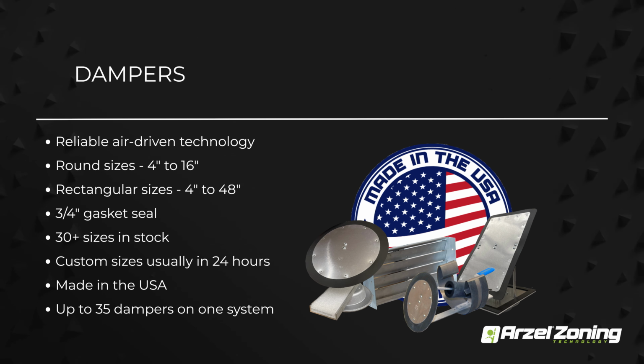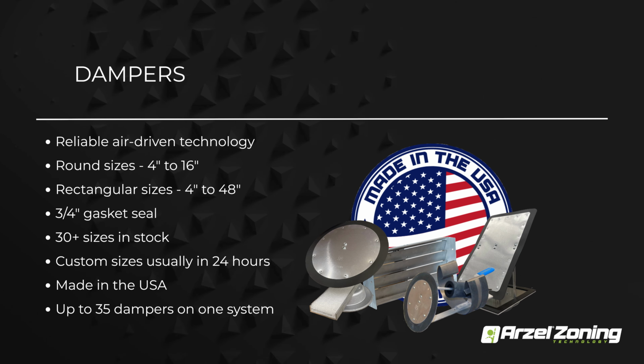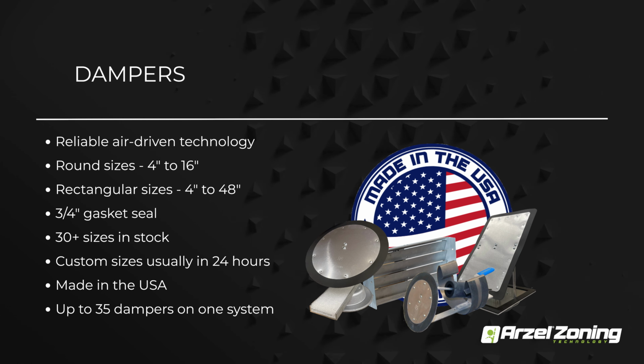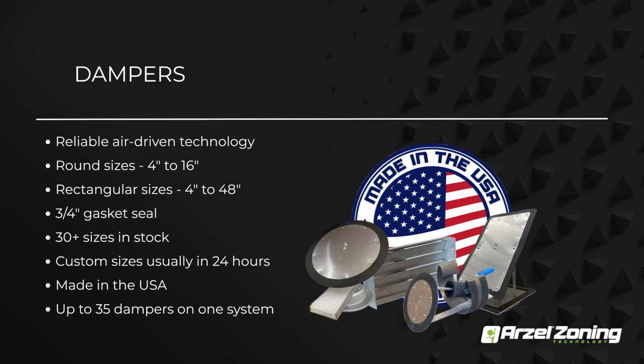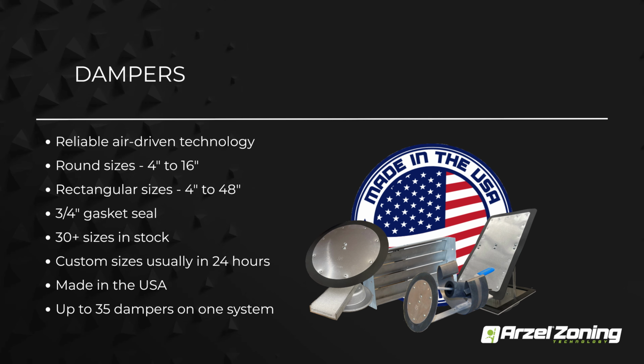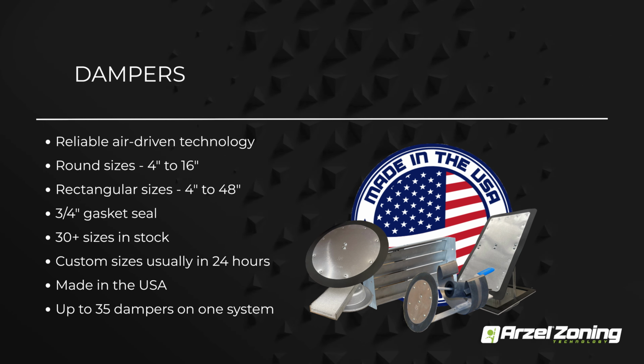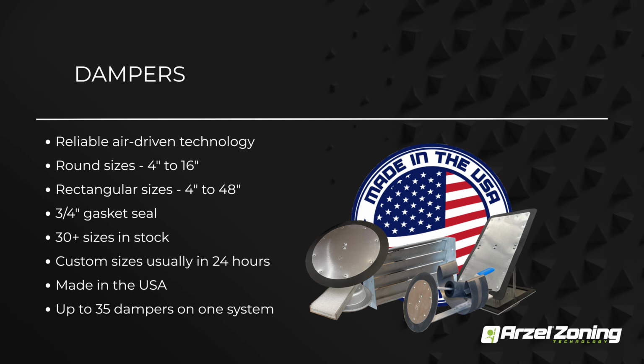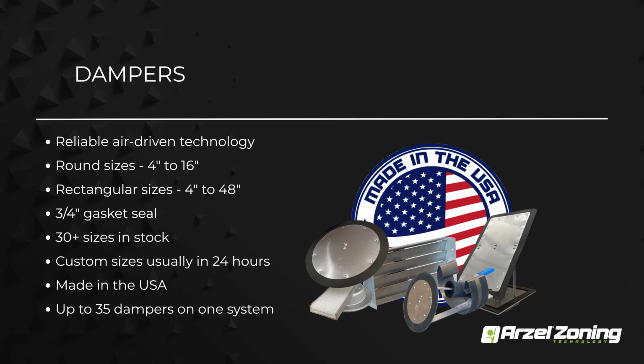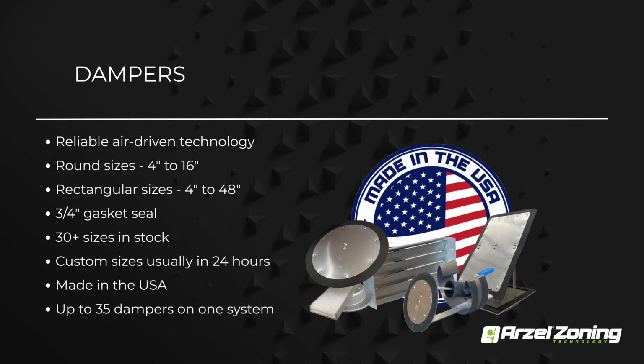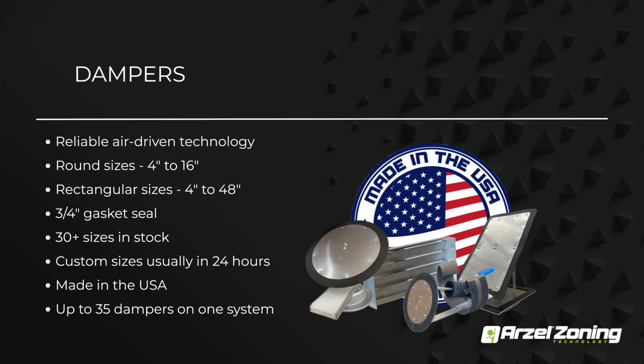Then as far as our dampers, we offer a number of different dampers, but our most common is going to be our easy slide dampers. These come in round or rectangular. They come in 4-inch to 16-inch on your round size and 4 to 48 on your rectangle. And then we do offer custom sizes as well. So if you have an oddball configuration, odd ductwork, oval, something like that, give us a call. We can actually make those dampers as well, and typically get them out within 24 hours of lead time. They're all going to have a 3/4-inch gasketed seal, so they're 100% closure on the dampers themselves.